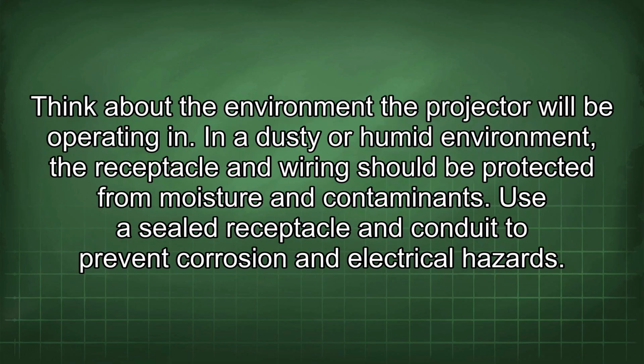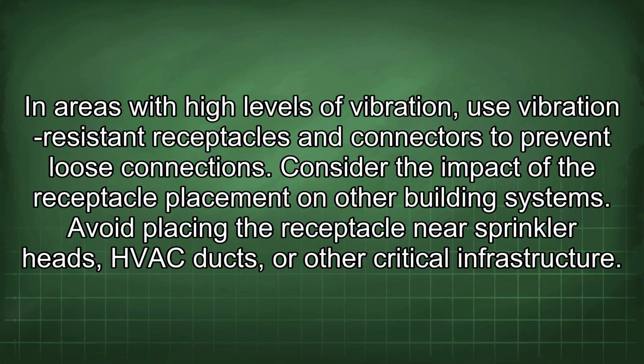Think about the environment the projector will be operating in. In a dusty or humid environment, the receptacle and wiring should be protected from moisture and contaminants. Use a sealed receptacle and conduit to prevent corrosion and electrical hazards. In areas with high levels of vibration, use vibration-resistant receptacles and connectors to prevent loose connections.